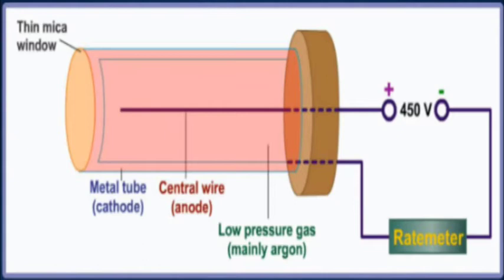The thin wire running inside the cylindrical part is the anode, connected to a 450-volt source. The connection going through the rate meter is the cathode — the negative terminal. There is a thin mica window on the left where radiation enters. Inside the tube, argon gas at low pressure is ionized by the radiation as it enters through the mica window. This ionization sets up an electric field between the positive and negative terminals, completing a circuit, and the rate meter counts the radiation being received.